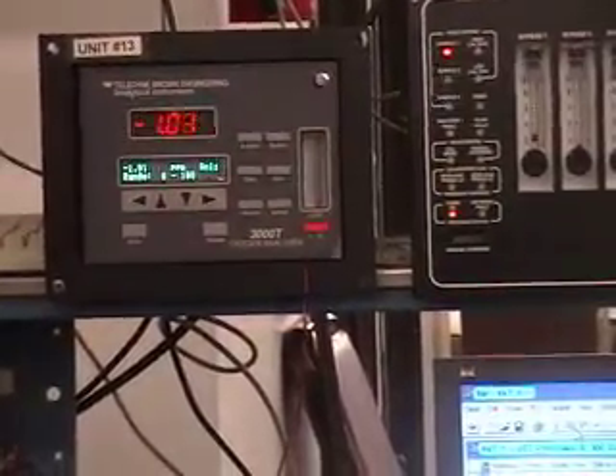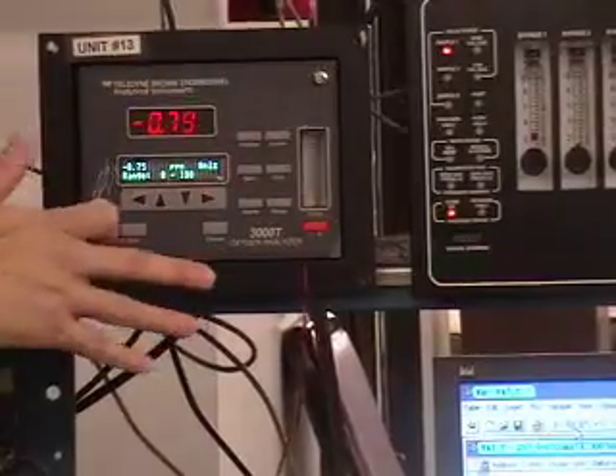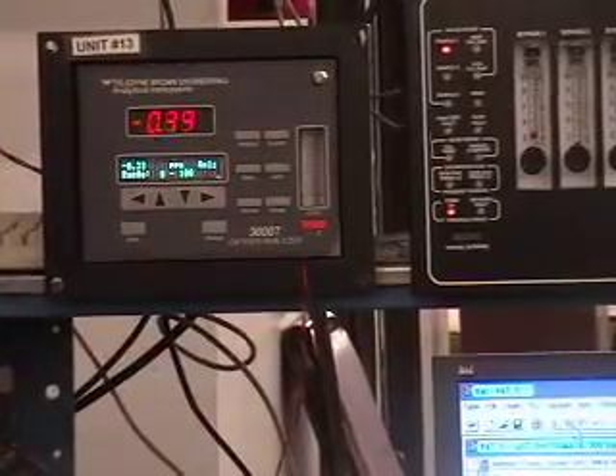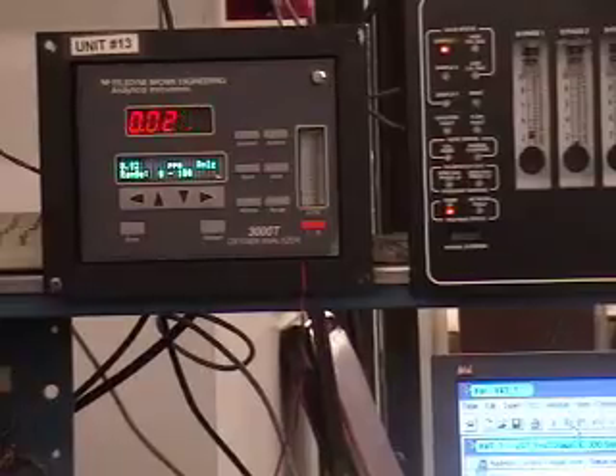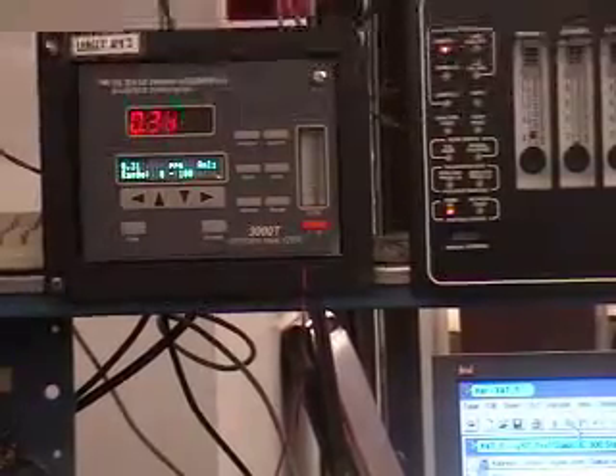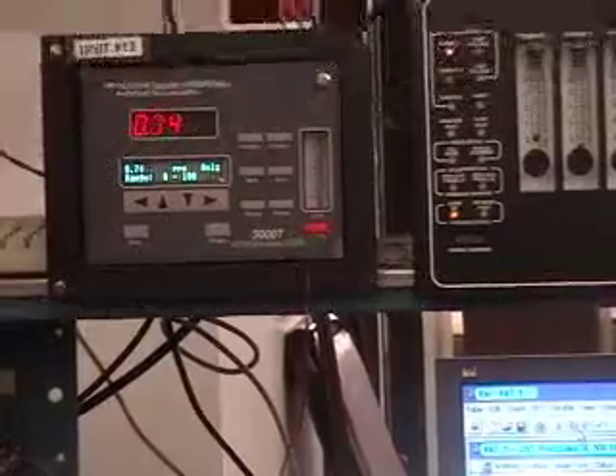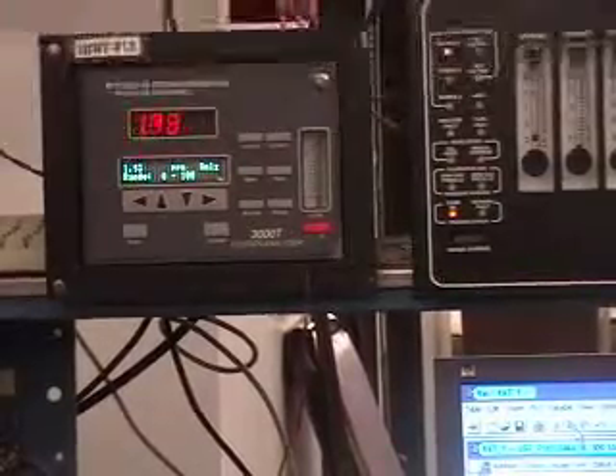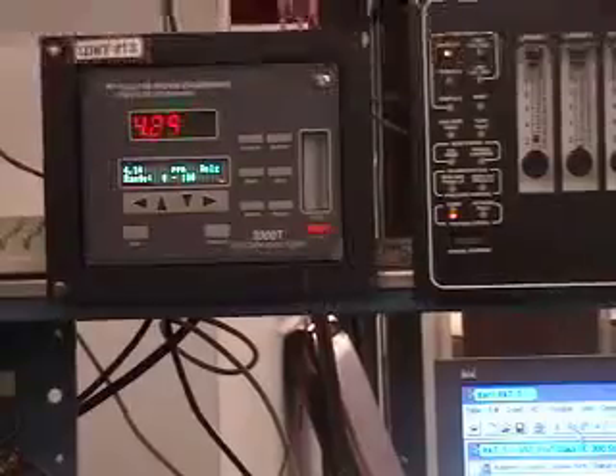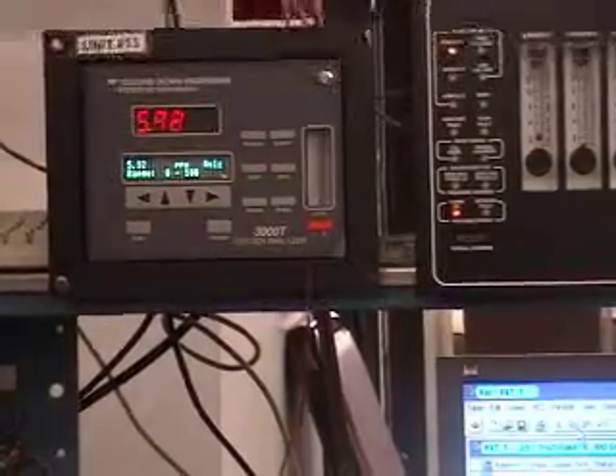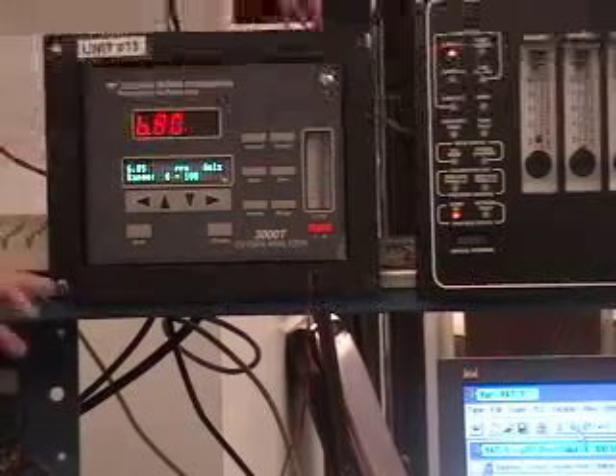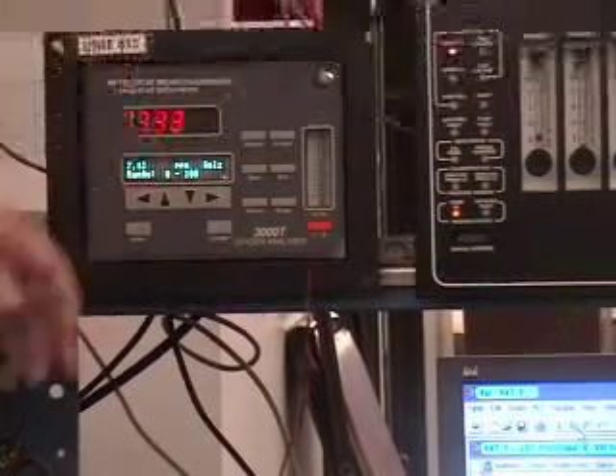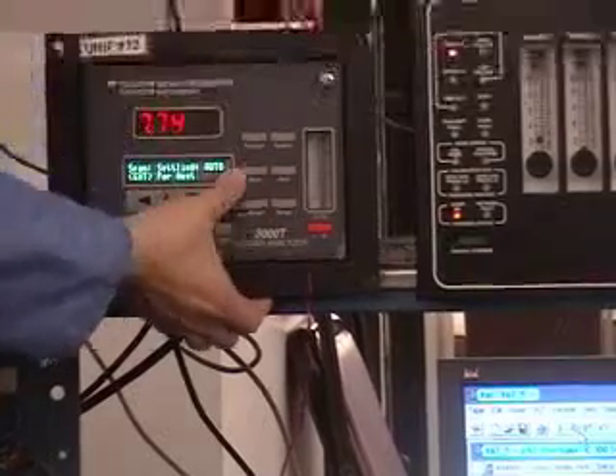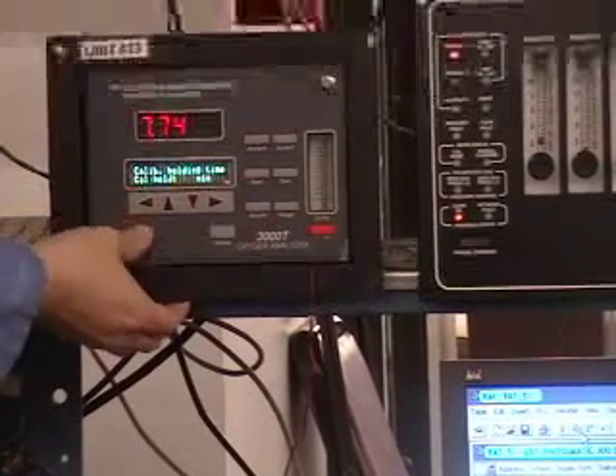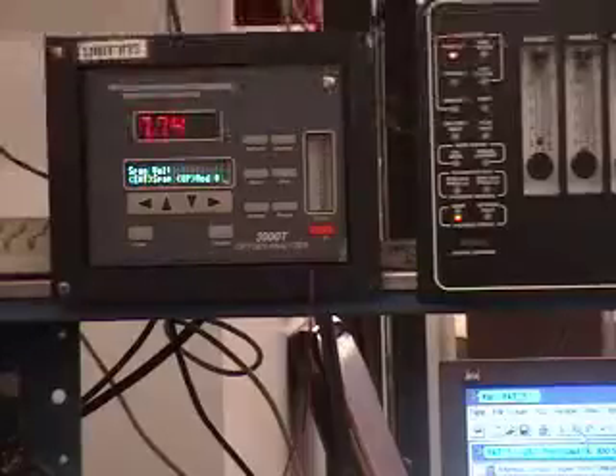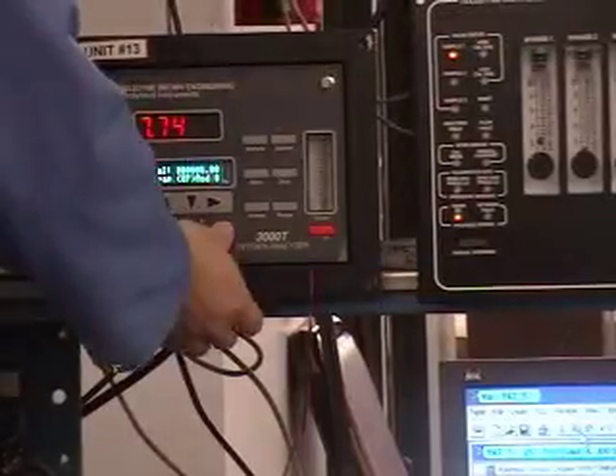The simulator has got to work its magic. Give me a number. Okay, here we go. We are going to get some reading. I'm going to send the command to do a span. The span is going to go to the value I already preset when I did it manually the first time, and I told it that the value was going to be 8 ppm. So it's going to span to the value 8 ppm.